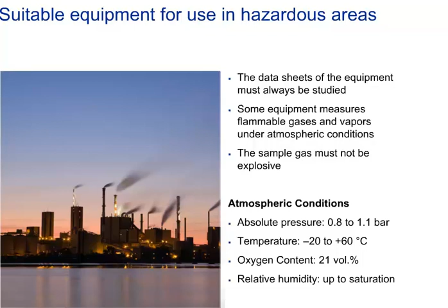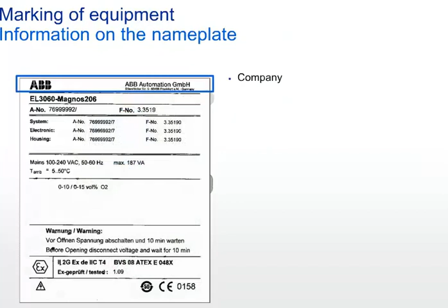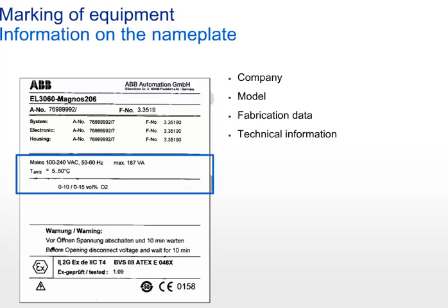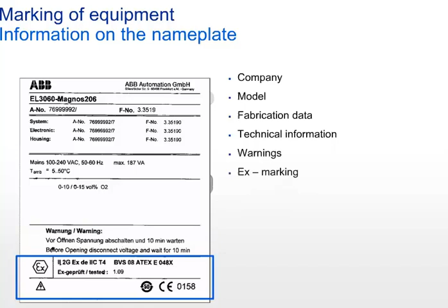Let's have a closer look at a typical instrument which is to be installed in Hazardous Areas Zone 1. On the side of the gas analyzer housing, you will find a nameplate with all the relevant information about the protection method and the suitable environment. On the top, you will find the company name, followed by the model name or number. Fabrication data, such as order numbers, allow the tracing of the products. Some technical information is given for proper installation and powering. Warnings to the operators to avoid risks during maintenance. Finally, with the Ex marking, you find details of the design and use of the analyzer in hazardous areas.